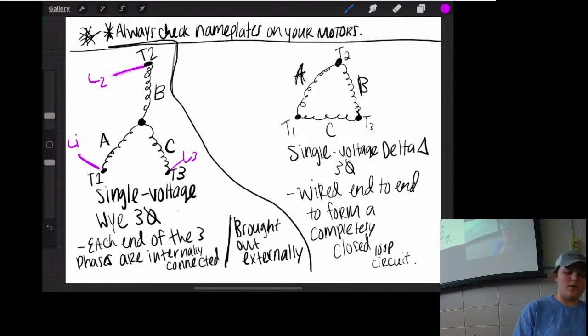Okay, so talking about single voltage three-phase motors, I'm just going to read you the definition out of the book: it's a motor that operates at only one voltage level. Cool, we understand that, single voltage, right? And they're less expensive to manufacture than dual voltage motors, but then again, they're limited to locations having the same voltage as the motor. So if your motor's only rated to withstand 240 volts, that's the only application you can use it in. So if your environment requires higher voltage, you've got to buy another motor - it's an investment.